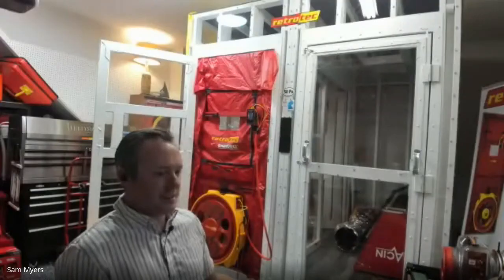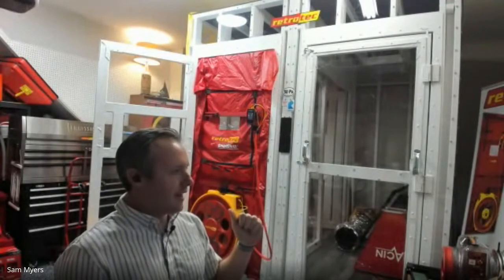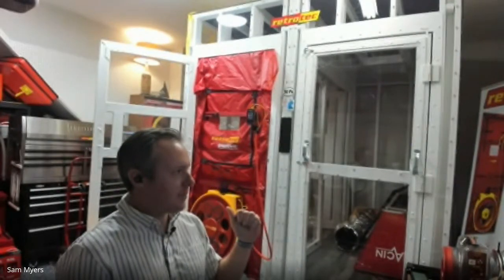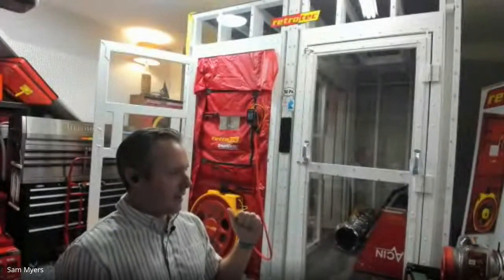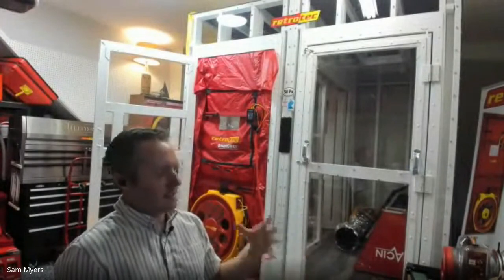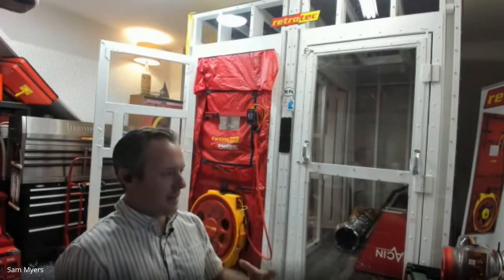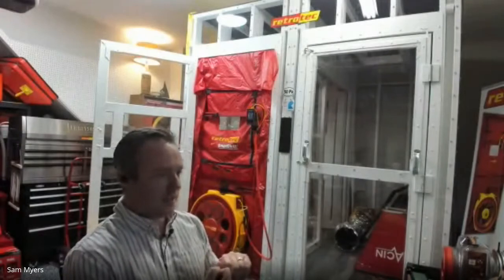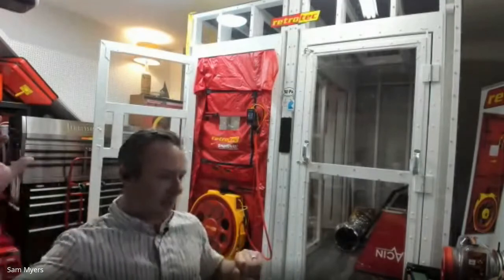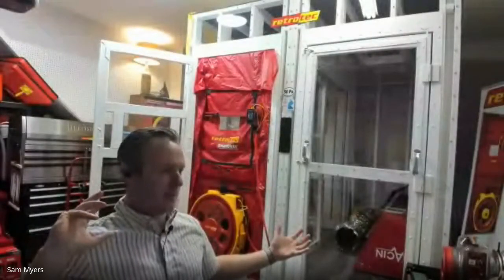Well, I think the energy and the comfort side is great, but I think a really important factor here is the health aspect of it. We had a customer in Oregon. It was a family of 5. They all had asthma. They were all on asthma medication, feeling horrible. And this is an HVAC contractor. He came in, did the blower door test, did an air leakage test on the duct system, and was able to find out that there was a very leaky ceiling plane and some very dusty cellulose insulation. And there was enough return leakage in there that was pulling dust from all of this attic insulation through the distribution system that these people were breathing in.